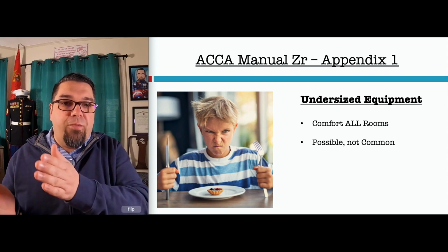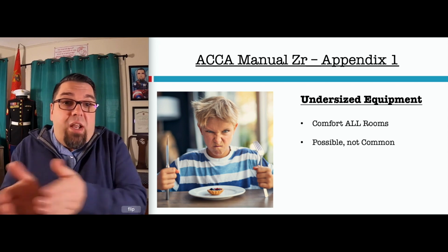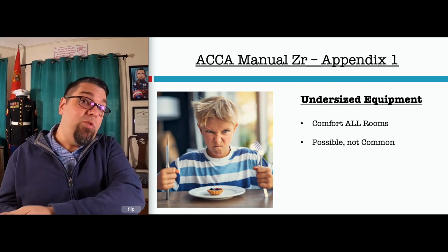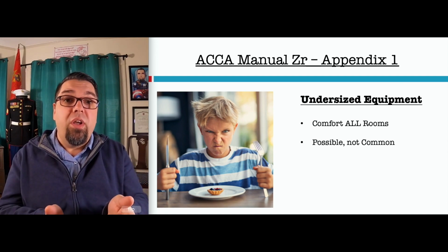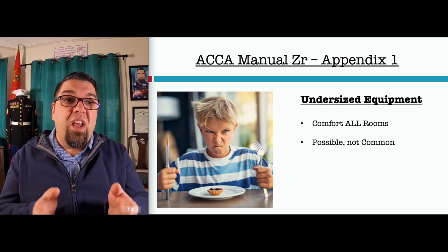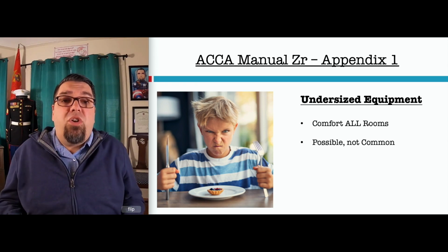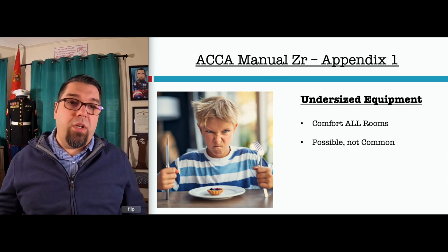If you're doing an aggressive load calculation, and it's going to oversize already by 20% of what's built in per Hank Rakowski, right? And then you can oversize slightly larger based on what's allowed by design and code in the Manual S process. If you put in undersized equipment, that is a huge mistake on your part. You couldn't do this if you're doing the process right. It's when people guess that they put in undersized equipment.